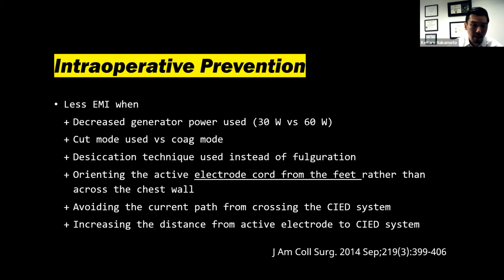So this study basically showed less EMI when there's decreased generator power used, 30 watts versus 60 watts, cut mode was used versus coag mode, desiccation technique was used instead of fulguration. And I'll review this, but desiccation technique is when the Bovie tip is actually touching the target tissue, whereas fulguration was when the Bovie tip is kind of hovering over it and letting it arc. Orienting the active electrode cord from the feet rather than across the chest wall.